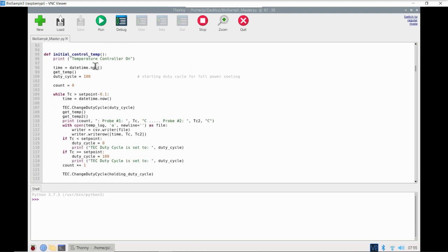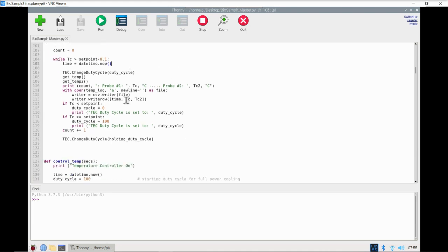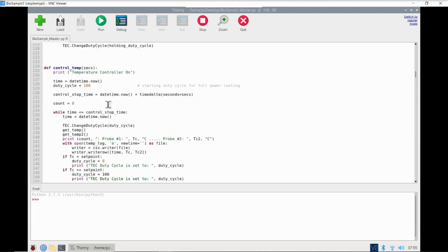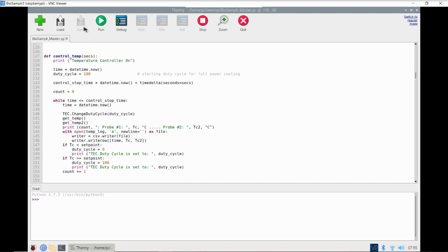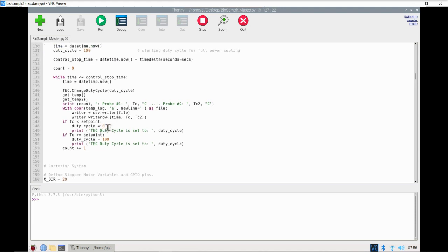Next we have initialControlTemp. This is one of the first functions that starts up with the process run. It's going to start by cooling the sample block with a duty cycle of 100%, cooling at its maximum rate, down to whatever the defined set point is minus 0.1 degrees Celsius. Once it reaches that temperature, it switches over to controlTemp, which runs for a defined number of seconds — the number of seconds between samples — and controls the temperature by turning the Peltier on and off above and below the set point.